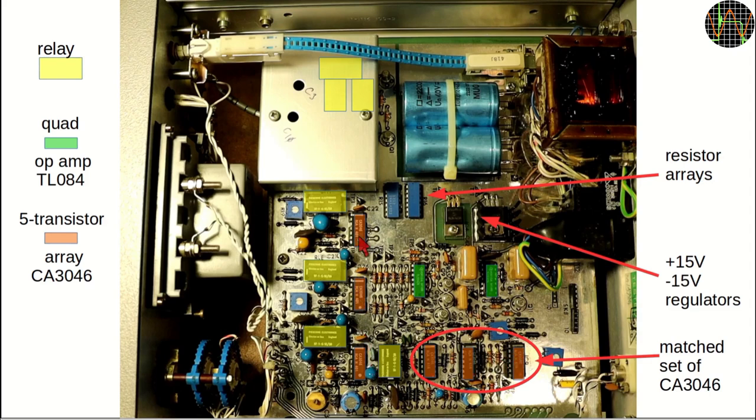Going even further, for this unit, Racal engineers measured the arrays to select 3 matching ones. Sadly, the manual does not say what criteria they were looking for. They have marked them with colored dots. One would need to replace them as a set to keep the performance in spec.